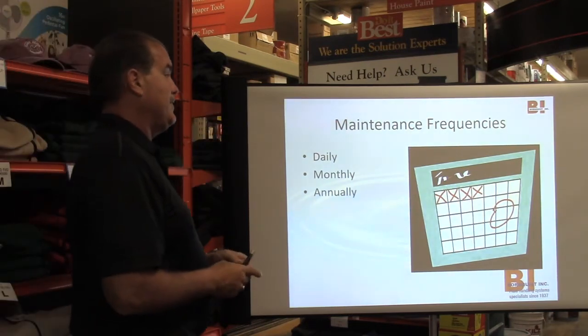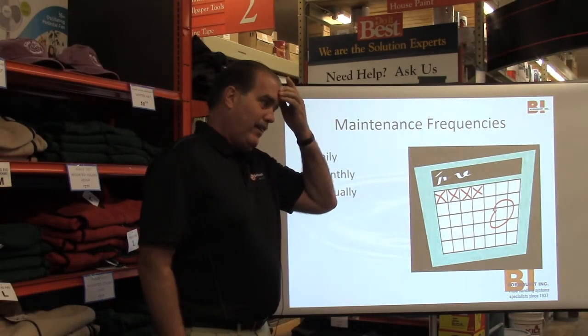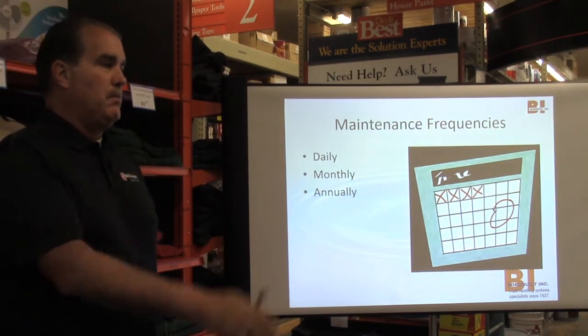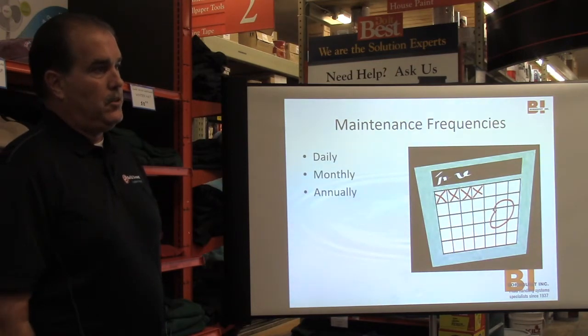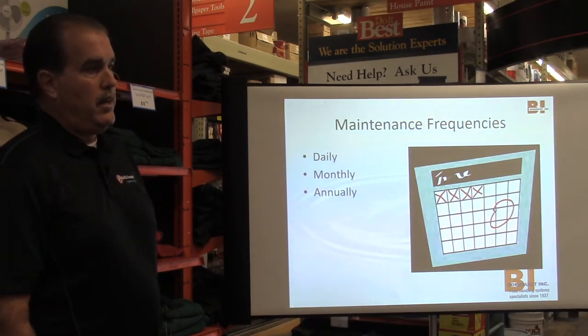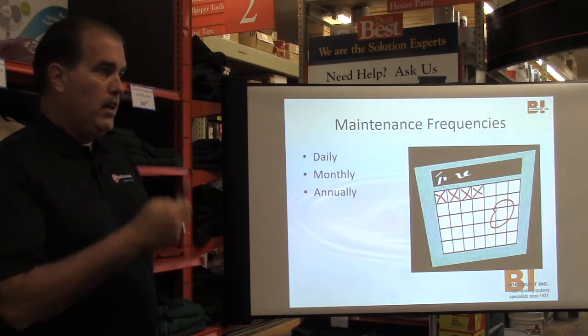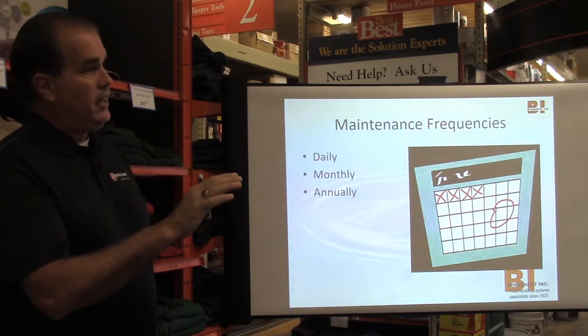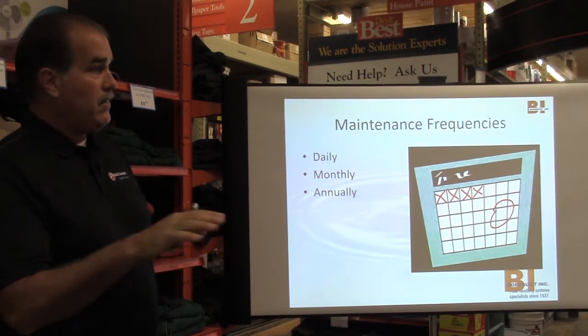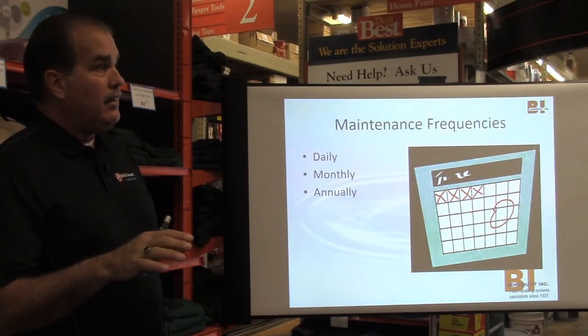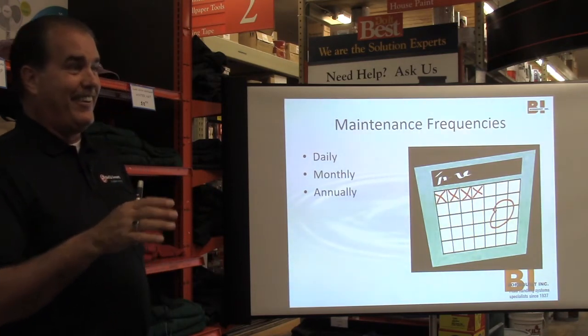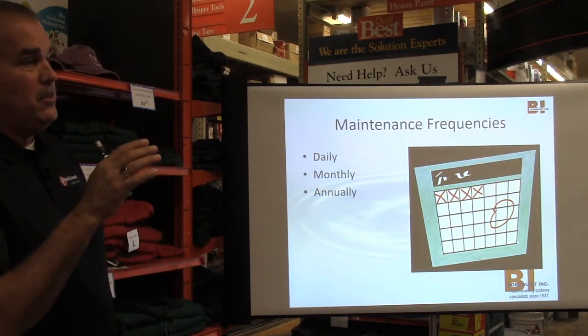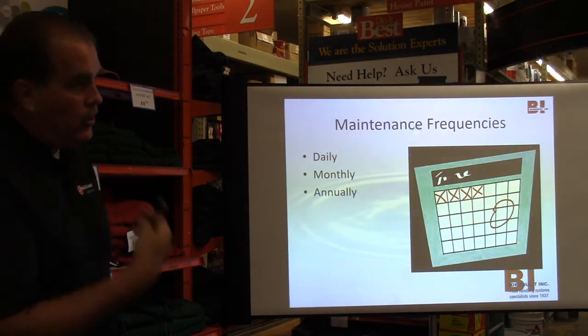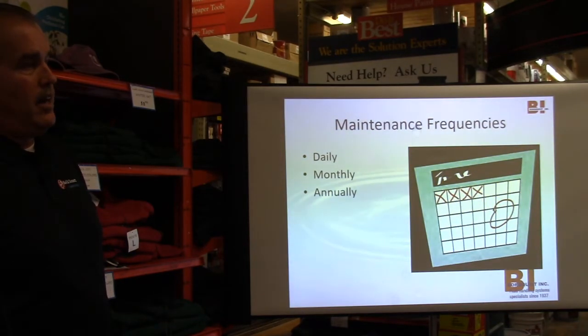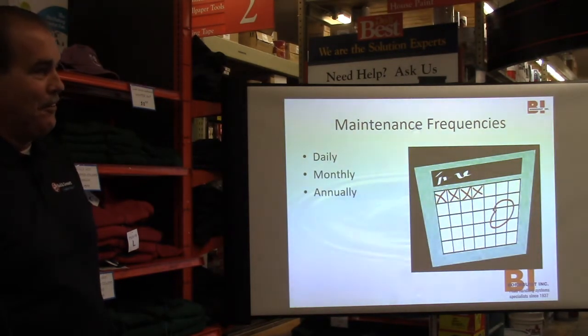The other thing, too, and this is where it's a little counterintuitive. You do it when the boiler's running and firing. Don't do it when it's just sitting there. You have no pressure. All you have is the weight of the water flushing. You want that pressure that's inside. Be careful now, it's hot. Wherever that water is going to go, it will burn you. However, you need that heat and pressure to get the good cleaning and a good flushing action. So it's counterintuitive because no one wants to do it because it's not an enjoyable event. It's not something you look forward to every week, I'm sure.